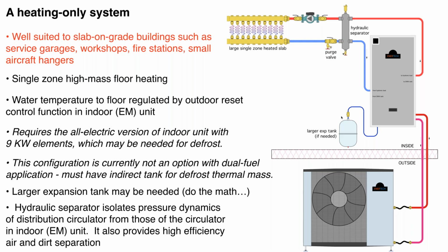And that's important because any air source heat pump does have to have a source of heat when it goes into defrost. When you have high mass slab heating, you have a lot of thermal mass out in that slab, actually an enormous amount of thermal mass. And the heat pump can draw from that mass the energy that it needs to melt the frost on the outdoor unit. It can also operate the 9 kW elements if necessary to get that heat. And in the case of a high thermal mass slab, you're not going to feel that. That's one of the advantages of air-to-water heat pumps versus ductless mini splits. With a ductless mini split, you don't have that mass. So when it goes into a defrost, that heat has to come directly from the conditioned space. So you're going to feel cool air coming out of those wall cassettes under a defrost mode of operation, okay?